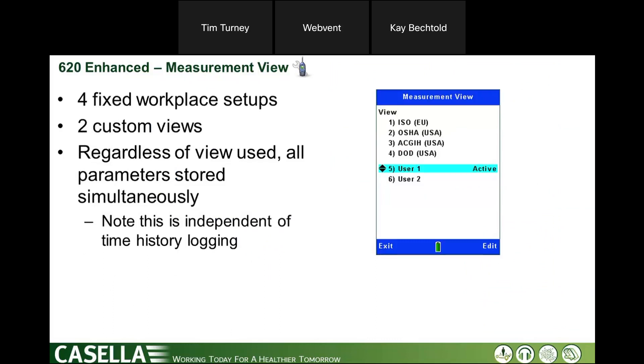From measurement view you can pick different measurement views — for example OSHA setups — or make your own with different parameters. Every time you boot up it will remember the last measurement view you were in. Importantly, regardless of what you select, it always stores every single parameter for all setups, so you can't make a mistake. Even if someone changed it, you can still download the data and get the results you want.